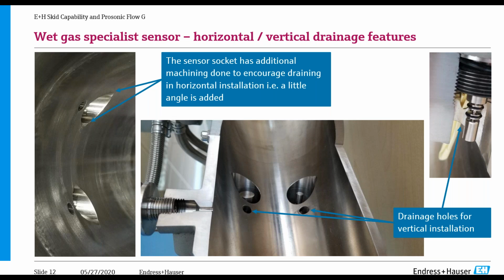And here's what it looks like in reality. So on the left side, you can see where the arrows are pointing. This is where we've machined inside. So if you put the transmitter on top or on bottom, it works both ways. We've machined so that condensate is encouraged to drop out of the socket there. And then we have the drainage holes. This was a cutaway demonstration model to give you a sense of how big the gap is. On the right side is the true transducer for that size meter. You can see it's quite a big gap in there. And then we have the drainage holes for the vertical installation for dropping the liquid out.